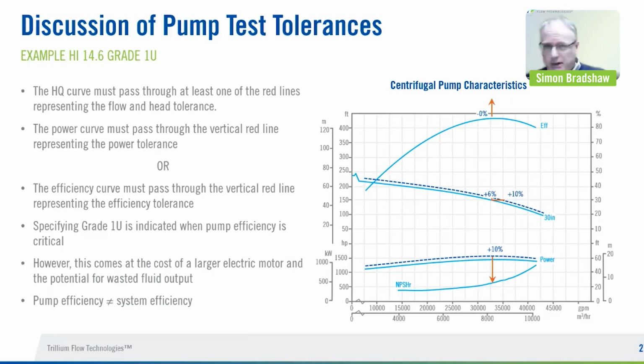That's fantastic. Why not specify this all the time? Well, in addition to the cost to the manufacturer of making sure that it hits that, there is another consideration that we have here. We do want to specify it when the pump efficiency is critical, but pump efficiency does not equal system efficiency. And as you can see on the graphic, when I specify 1U, it's quite likely that my head and flow is going to be higher than the notional sales curve, and also my power is going to be higher.